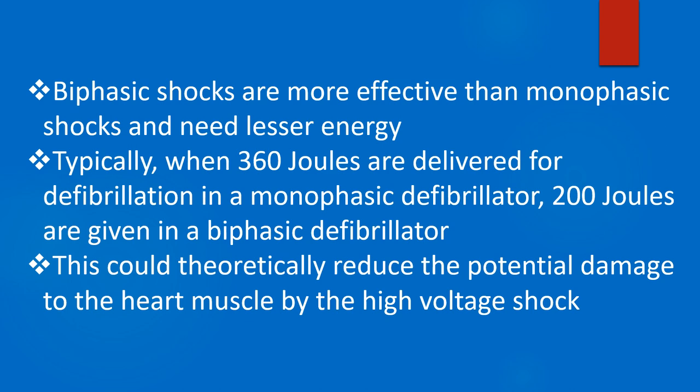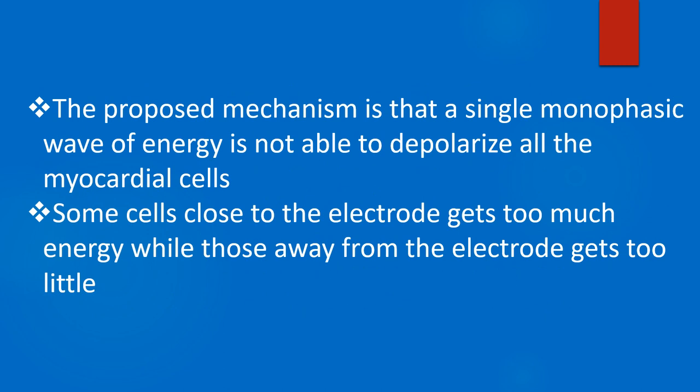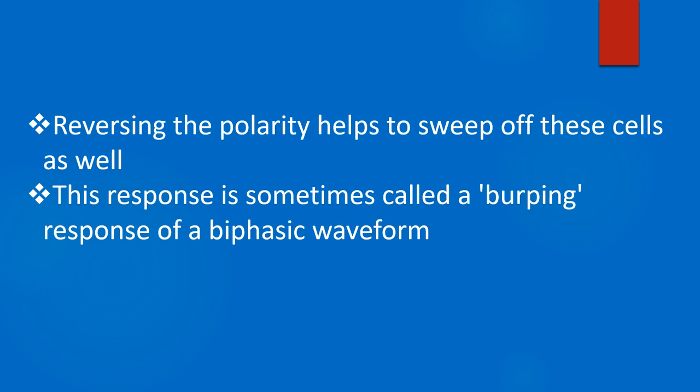This could theoretically reduce the potential damage to the heart muscle by the high voltage shock. The proposed mechanism is that a single monophasic wave of energy is not able to depolarize all the myocardial cells — some cells close to the electrode get too much energy while those away from the electrode get too little. Reversing the polarity helps to sweep off these cells as well, a response sometimes called the burping response of a biphasic waveform.